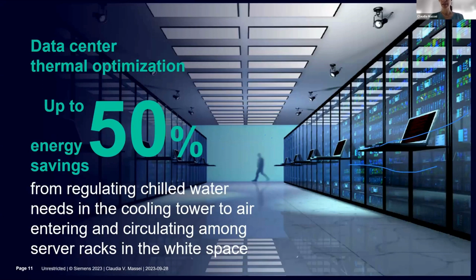Another thing that makes the data center tricky is that it's quite unpredictable which part is going to be heating up more at a given moment, because it depends on which server has more load at a certain time. That's why you need some sort of artificial intelligence, because you need your whole system to react in real time to the changes. If one unit has a higher load and is heating up more, you need to make sure the cold air comes there first to bring the temperature down.